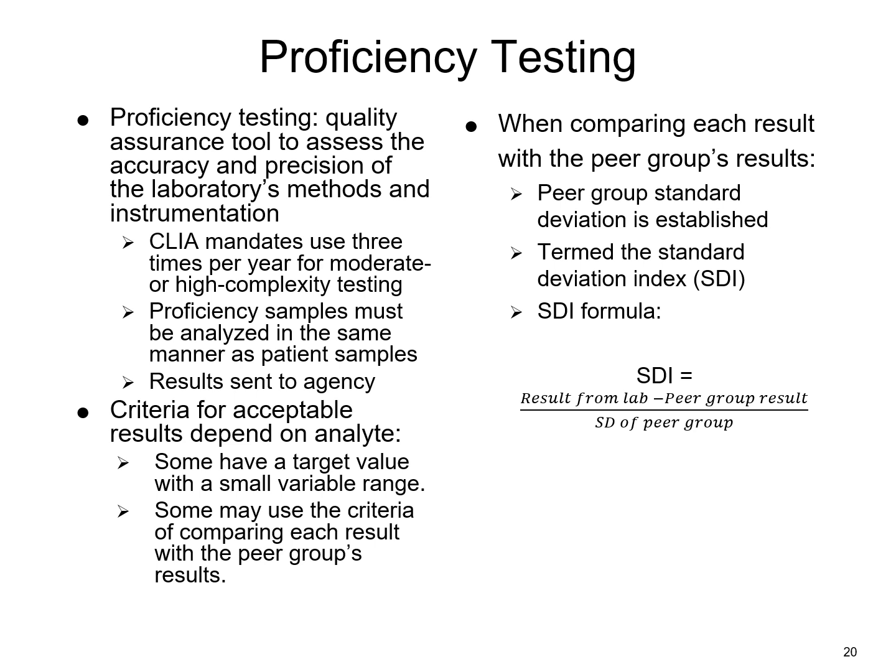And so there are some different values that we look at. Of course, you need to pass, and there are some criteria there that determines whether or not you pass. If you have a failure, you do have to address it. You do have to make notations and investigate why that failure happened anytime you get a result incorrect. But what you're looking at when you're looking at those results and comparing them with your peer results is there's a standard deviation index formula that is used that looks at your results compared to your peers' results. So it just kind of gives you a report card of where you stand in the bigger picture when you're comparing yourself or your laboratory against other laboratories.